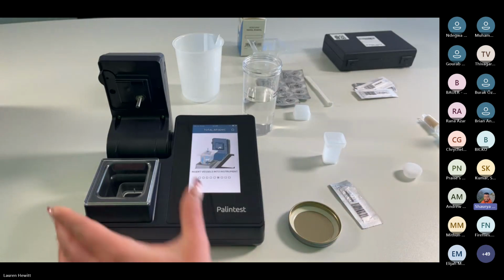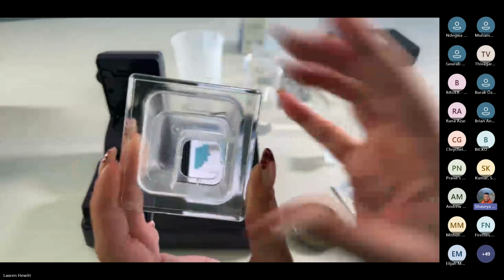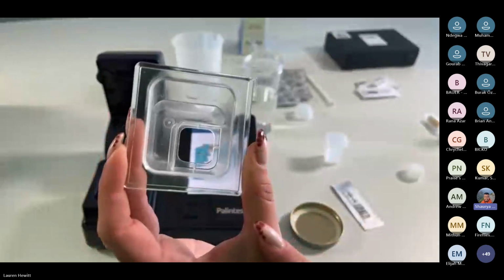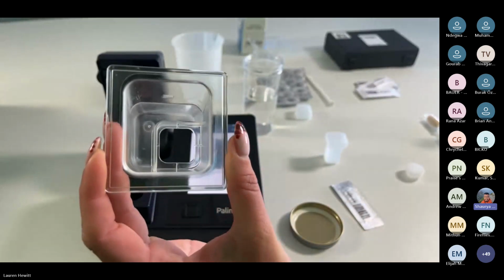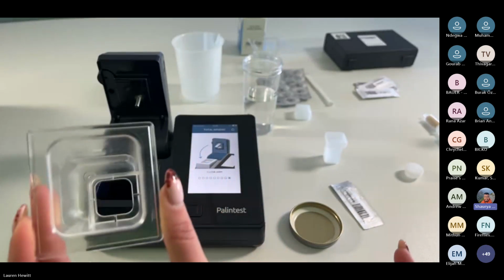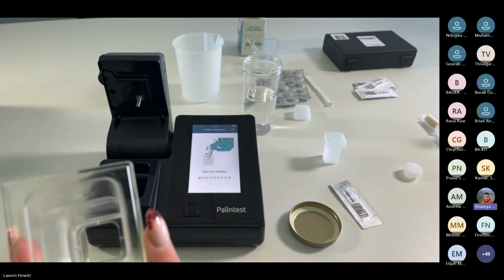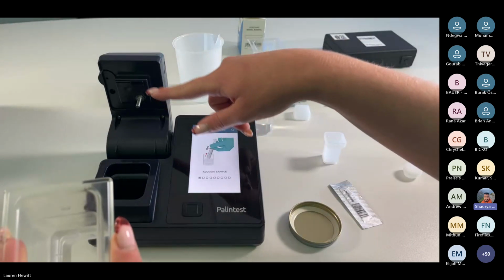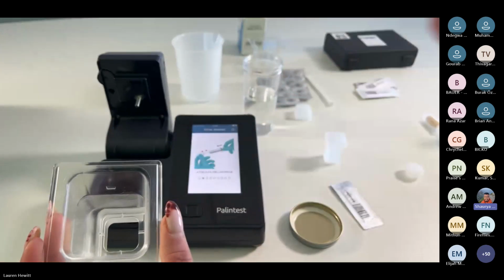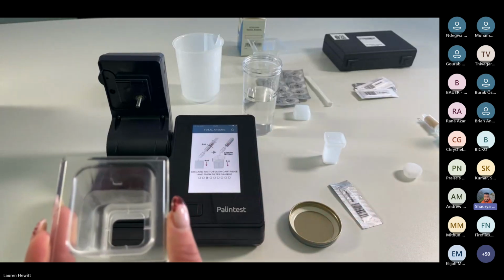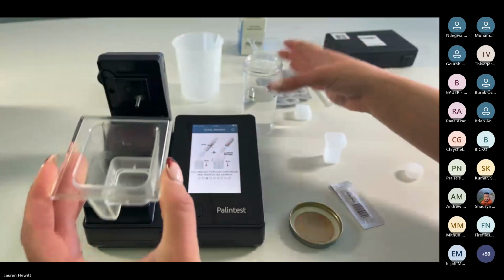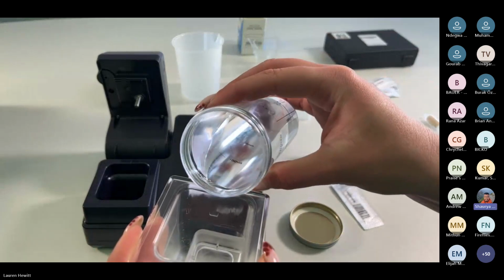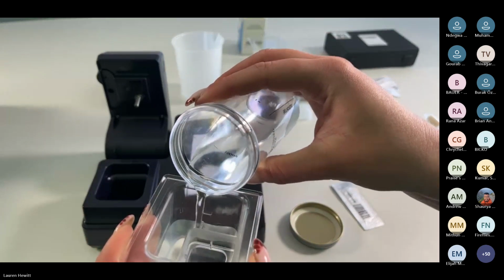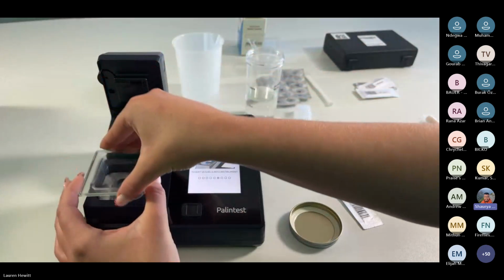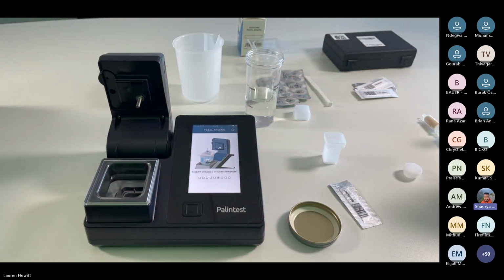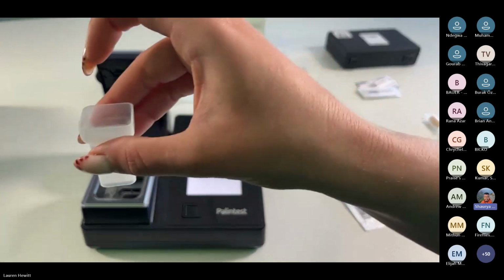Now the other part that needs to be filled here is the sample vessel. You will see this holder is where the vessel goes in that we've just prepared. The outside container must also be filled with the sample. This doesn't need to be passed through the filter because this is just where the temperature probe is inserted. This is the temperature probe on the device here, and you need to make sure that the same sample that is in here is the sample that is being passed through the filter so that it is a consistent temperature. So you would fill in the outside up to the neck of the sample vessel, insert that into there, and then now we have the sample pot here.